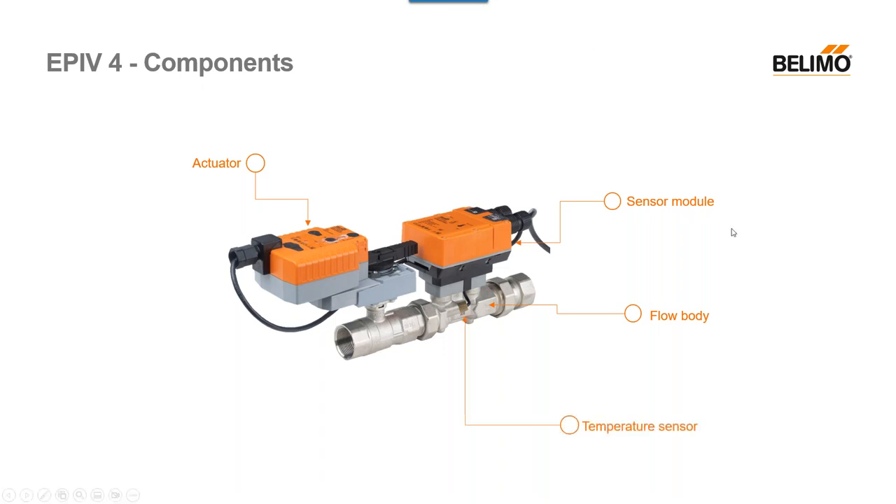Next is our temperature sensor. We did have a temperature sensor in the EPIV 3s — that was mainly for glycol compensation previously — but we did not have a feedback or output signal previously. With the new EPIV 4s, we do have that capability; it reads temperature in that section and you can see that in our system app as well. I want to make note that this is different from the energy valves, which actually come with two temperature sensors — this does not, so there's sometimes some confusion there.